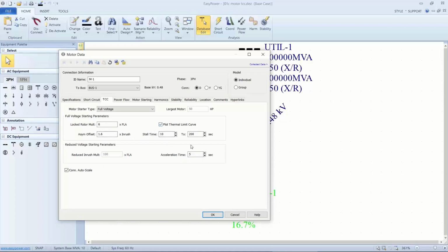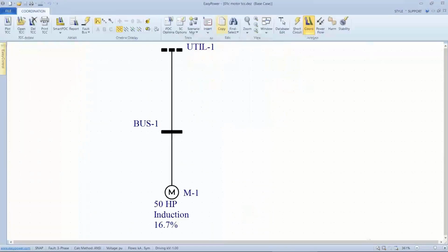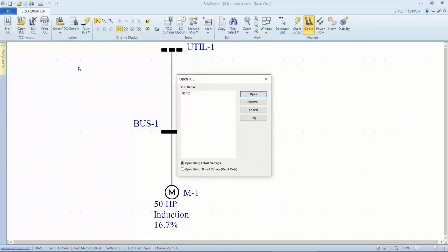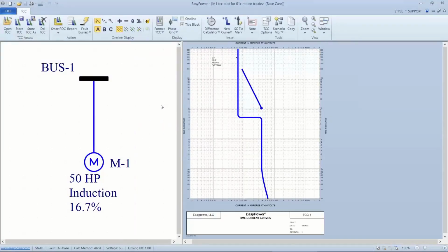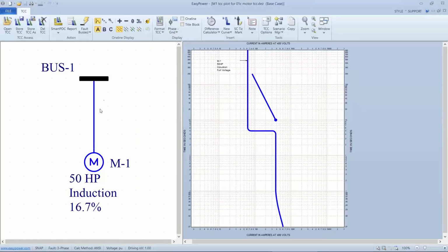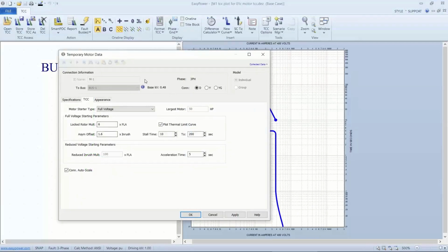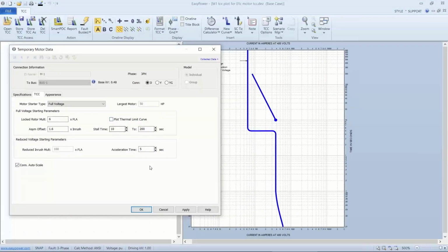Here's where we're plotting the thermal curve. So let's go ahead and plot this. I've already plotted and saved it, so I can come back and open it up. And it looks a little bare without the text there. But if I go back and open the dialog box, you can see that my thermal limit curve appears because this checkbox is there, and it's being plotted with these parameters from 10 seconds to 200 seconds. Acceleration time was 5 seconds. If we have a quicker acceleration time, we can put in 3 seconds. Expect the motor acceleration to reduce.